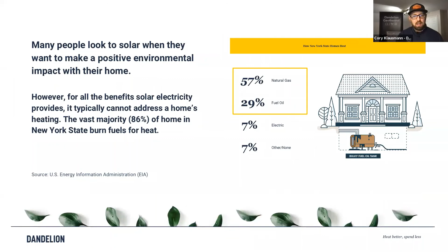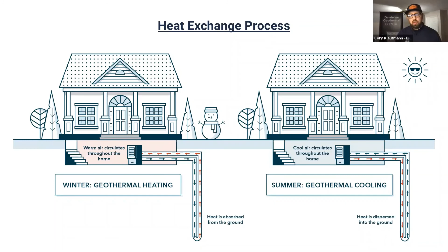We can go past this slide and the next one, let's keep going. Our process: we identify an area on the property. We do have some setbacks we have to abide by here in New York. We try to stay at least 15 feet away from the foundation when we're driving our drill rigs and drilling the borehole, 50 feet away from a septic tank and leach field, 25 feet away from a well, and 10 feet off the property line.